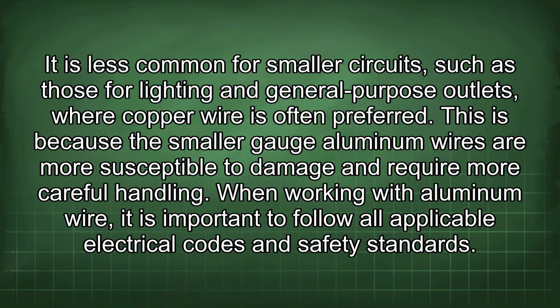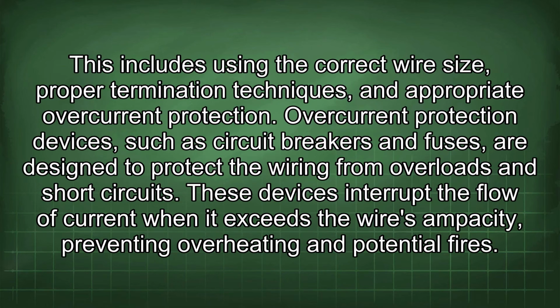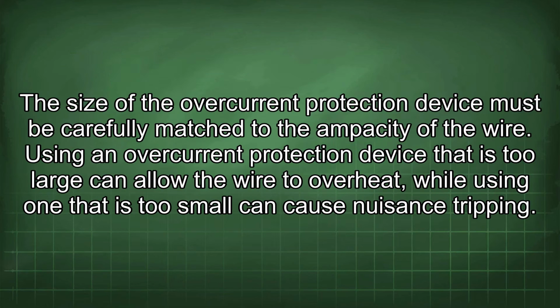When working with aluminum wire, it is important to follow all applicable electrical codes and safety standards. This includes using the correct wire size, proper termination techniques, and appropriate overcurrent protection. Overcurrent protection devices, such as circuit breakers and fuses, are designed to protect the wiring from overloads and short circuits. These devices interrupt the flow of current when it exceeds the wire's ampacity, preventing overheating and potential fires. The size of the overcurrent protection device must be carefully matched to the ampacity of the wire.